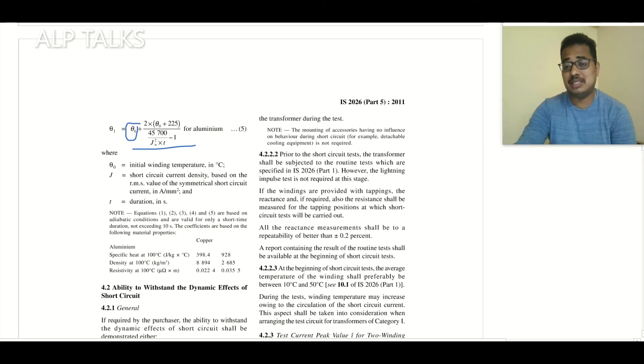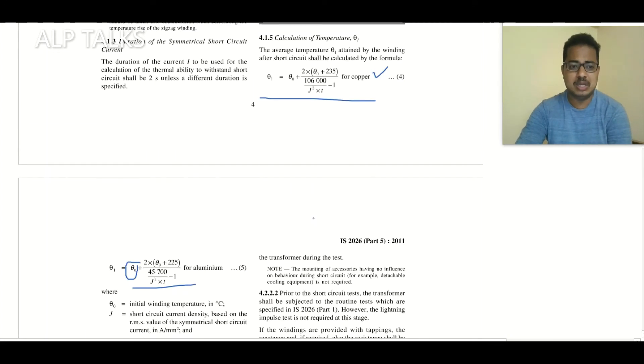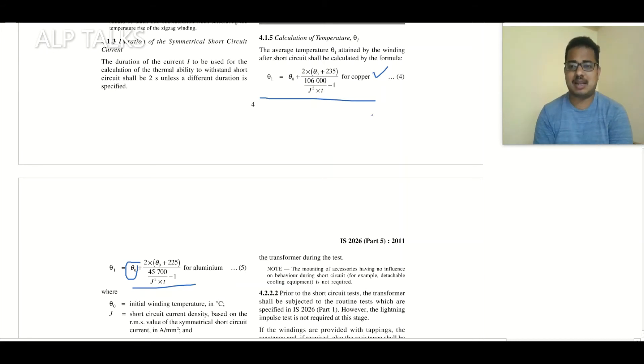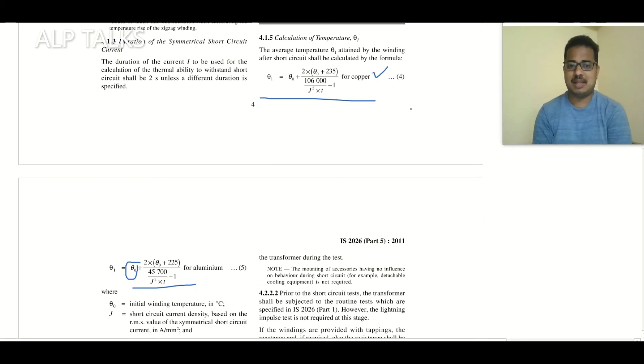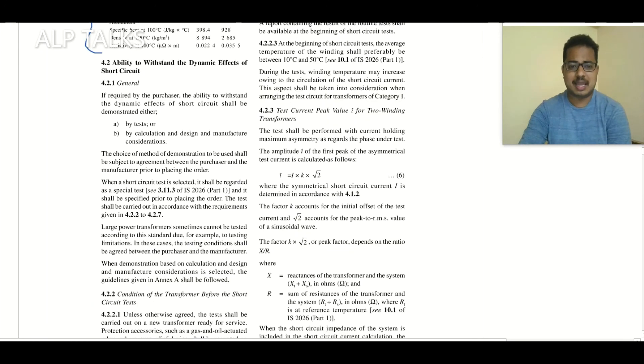In this formula, θ_naught is the initial temperature, j² is the current density during short circuit conditions, and t is the duration. This checks whether the conductor will melt if that much current flows — it is for thermal assessment, not dynamic. Both designers and customers can use it to assess whether the chosen conductor cross-section is correct.